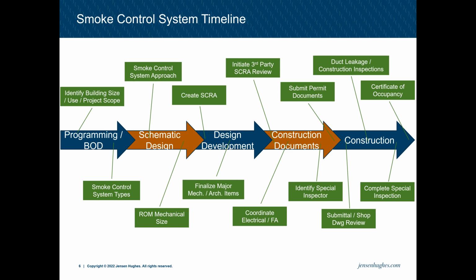Then throughout design development, that's when you start to finalize the major mechanical and architectural features for smoke control. Where exactly the fans are, making sure you have sufficient space for those fans, etc. So then the project would move into construction documents. Massachusetts requires a third-party review of the smoke control rational analysis if it's using the exhaust or pressurization method. So that's typically for atriums and stages that Tony will talk about.